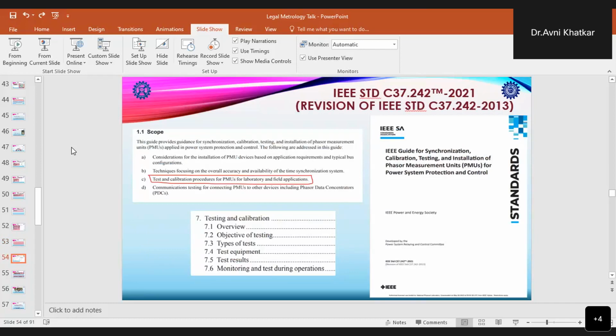IEEE also issued a guideline for the synchronization, calibration, testing, and installation of PMUs for power system protection and control. This is the IEEE standard C37.242 2021 standard. It is the revision of the 2013 standard, and it provides the guidance required for the test and calibration procedures for PMUs for laboratories and their field applications.